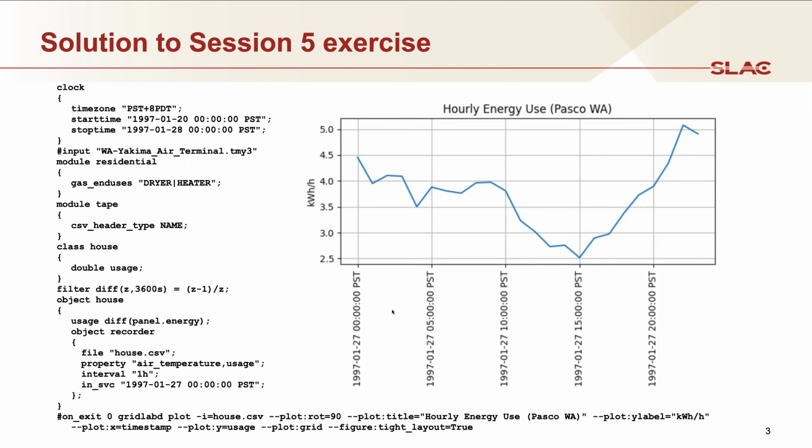Often when you generate these plots, we really want just the plot and no extra space around it, because we put them into reports and things like that. This avoids you having to clip or do any kind of cleanup afterwards. And so as you can see, the result is something fairly typical for a winter energy use. There's more energy use at night with the heating related things, and then there's less energy use during the day. So you see some lighting load and other things that are related, but generally this gives you a sense of what we're getting from a system like this.